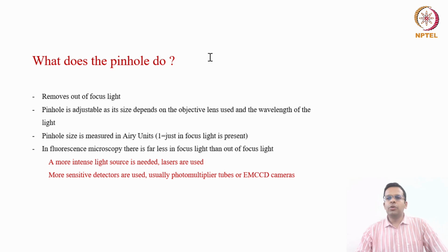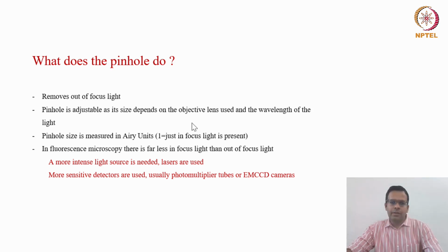So what does the pinhole do? As we just discussed, the pinhole removes the out of focus light. It is adjustable, as its size depends on the objective lens used and the wavelength of the light. Pinhole size is measured in Airy units.